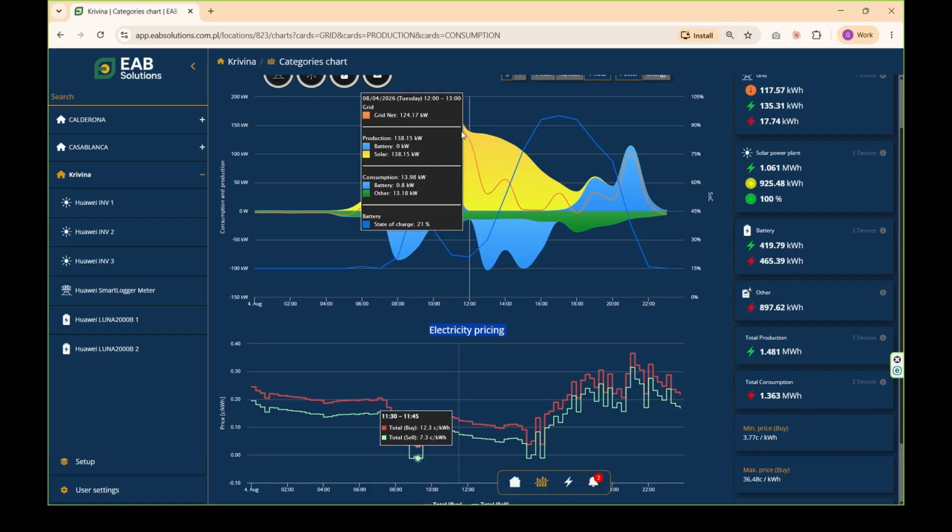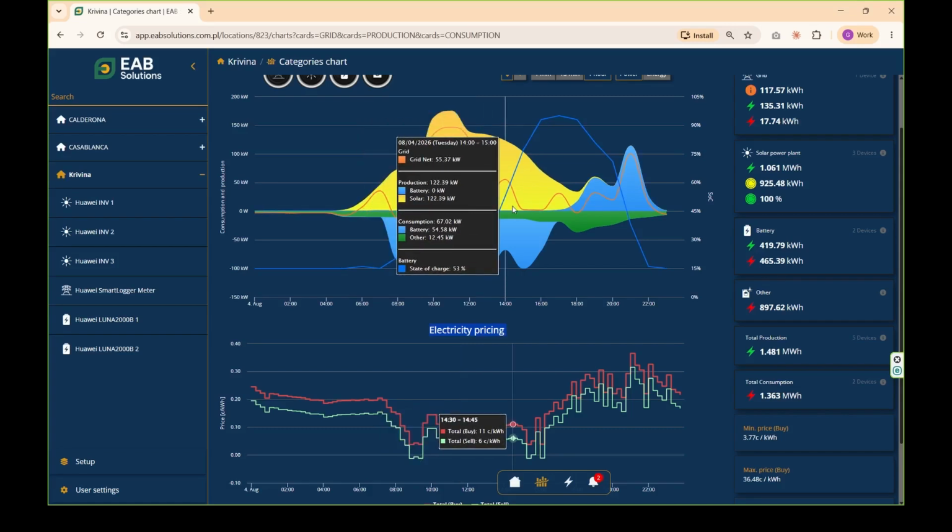Of the 2 levers we use, one is on-site energy production consumed by the client. The second is arbitrage or peak reduction. That lever, for example, the client's peak reduction, we'd still be able to do because it simply works by monitoring the client's meter. It doesn't need internet. That would keep working too. The client's peaks would be reduced with or without internet. The internet mainly only affects knowing the electricity prices. Once the internet comes back, we have the electricity price information and everything works perfectly again. And there's no problem at all.